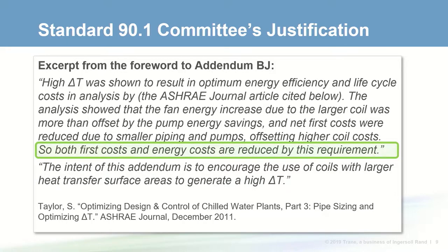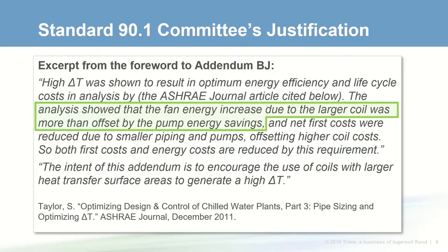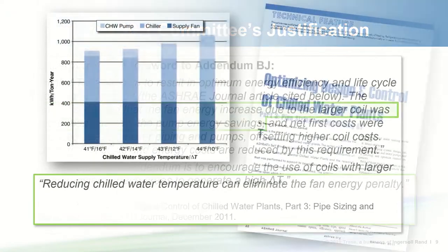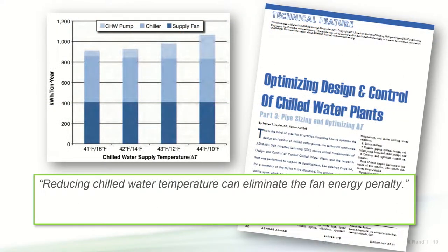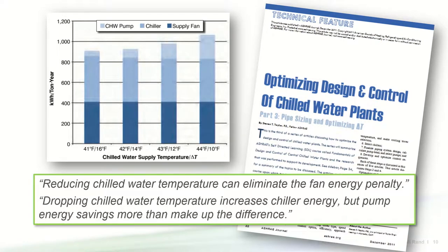The analysis showed that designing a chilled water system for higher delta T reduced first costs due to smaller valves, piping, and pumps, and also reduced energy costs. The results showed that the increase in fan energy due to added coil surface was more than offset by the pump energy savings. The article also showed that using a slightly lower chilled water supply temperature would allow for a coil selection with no impact on supply fan energy — no change in surface area or air pressure drop — and the pump energy savings still outweighed the slightly higher chiller energy.